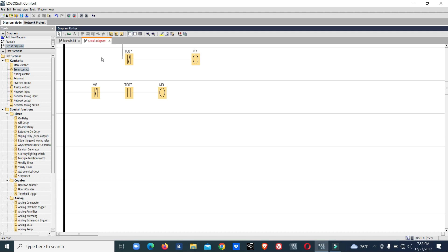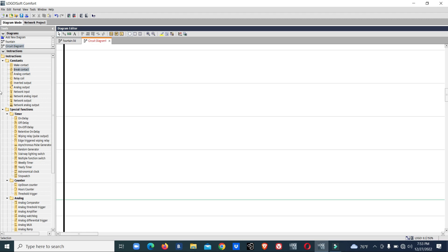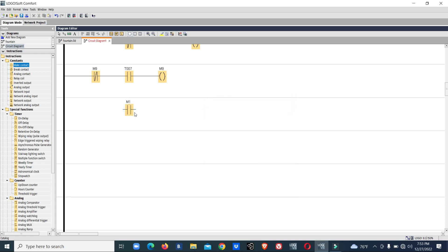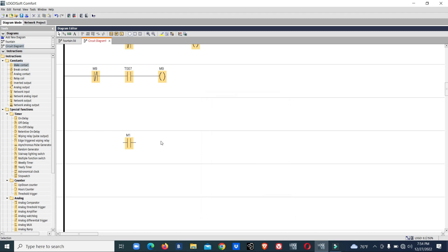Output one is for light set one, output two for light set two, output three for light set three. We will keep M1 — M1 is for a single on contact. M1 is for light one, M2 for light two, M3 for light three, and M4 for light one and two. So we will keep M4 also for light one and two.